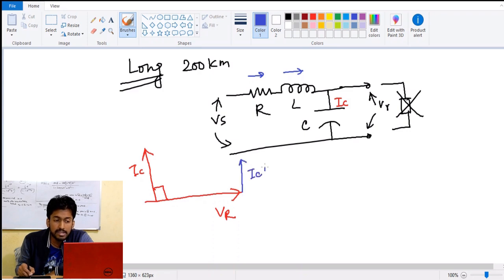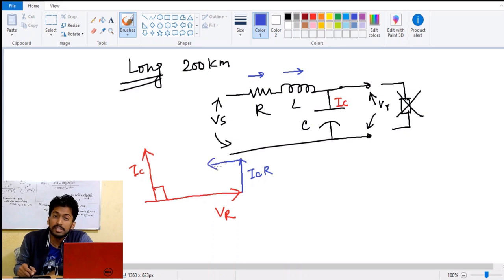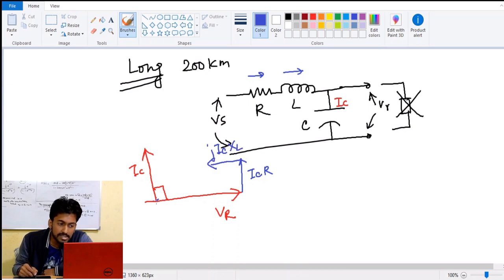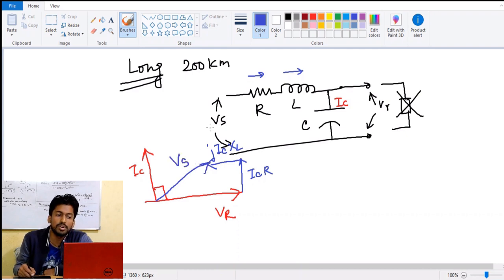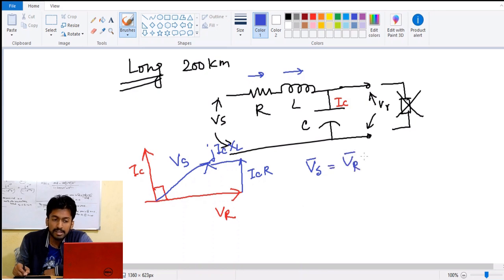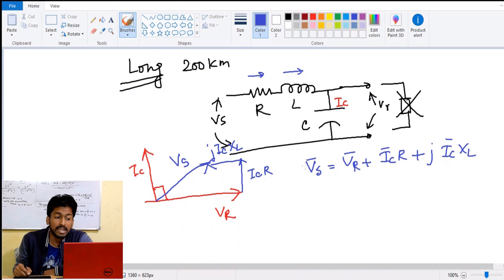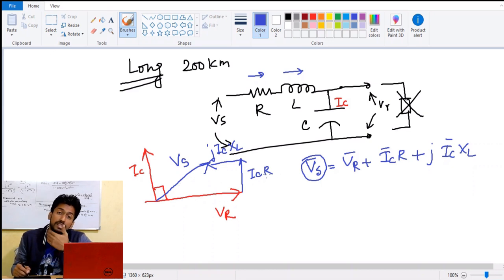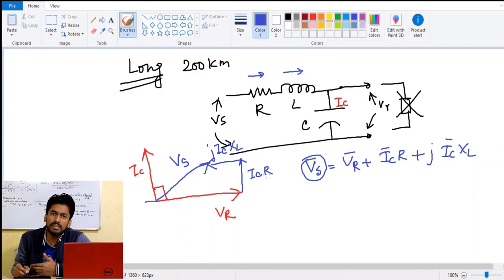The voltage drops are: Ic × R, which is the resistive voltage drop, and Ic × XL, which is a 90-degree leading voltage drop — a j term representing a 90-degree phase shift. The summation gives the net sending end voltage: Vs = Vr + Ic·R + j·Ic·XL. The magnitude of Vs is actually lesser because of this current shift. This is the Ferranti effect — the sending end voltage becomes around 5% to 10% less than the receiving end voltage, due to the charging current present in the circuit.